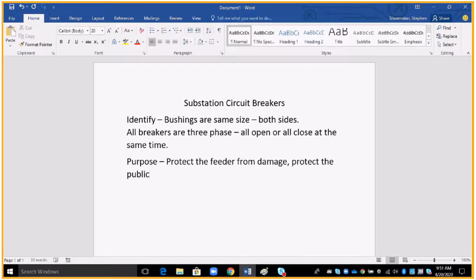Again, if it falls on something or falls to the ground, we need that circuit or wire to be de-energized as quickly as possible so the public doesn't come around and have an energized circuit. And lastly, protect the substation. Definitely don't want that fault to go back into the substation and then back to the substation transformer, and our next protective device would be the ACI. So it's a little bit of protect the substation and the transformer, line isolation. So if that breaker opens, the rest of the breakers can keep on going in the substation, and I've isolated that feeder circuit. And then I'll have to effect repairs. So the purpose: protect the feeder from damage, protect the public, protect the substation, and line isolation.